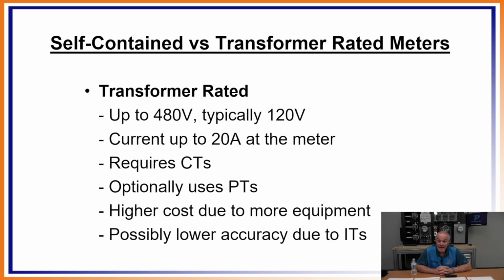To get it down to 20 amps, the next point says it requires CTs. If I've got a 1,000 amp service out there, I've got to get it down to 20 amps, because, remember, that's what's available at the bottom of the pole. All the smaller rated stuff means we can make everything smaller. The little test switch and so on don't need big blades to handle 1,000 amps, or any kind of interrupters for you to be able to work on that equipment. So we transform it down to the 20 amps.